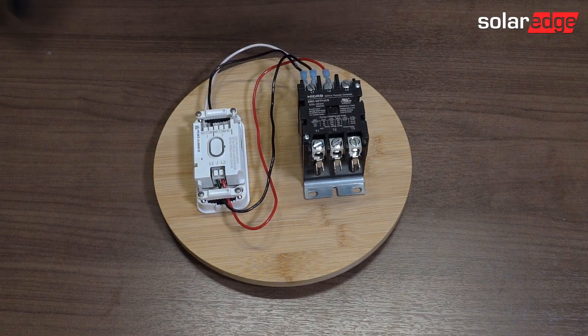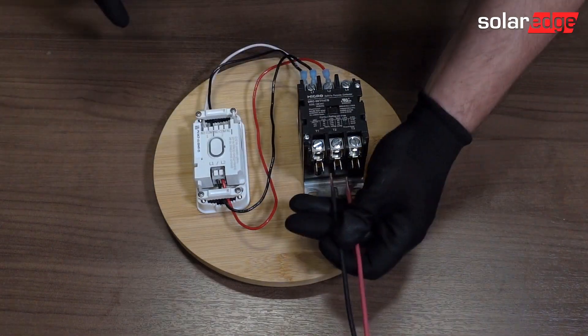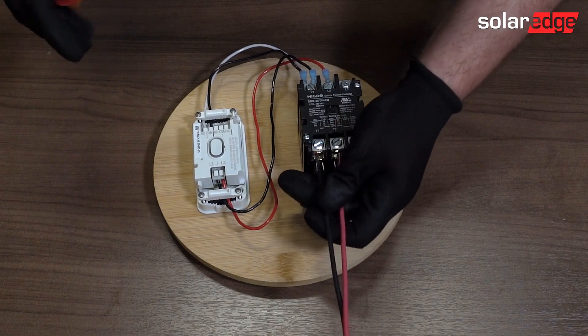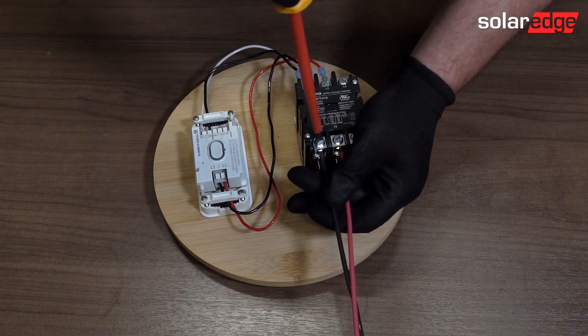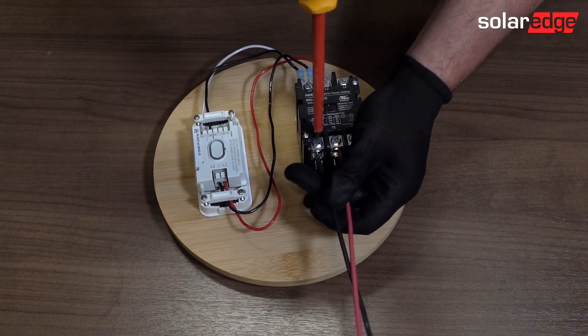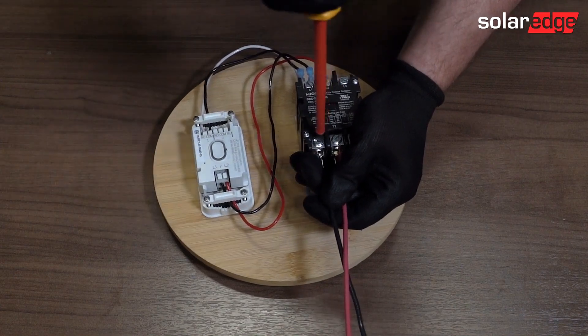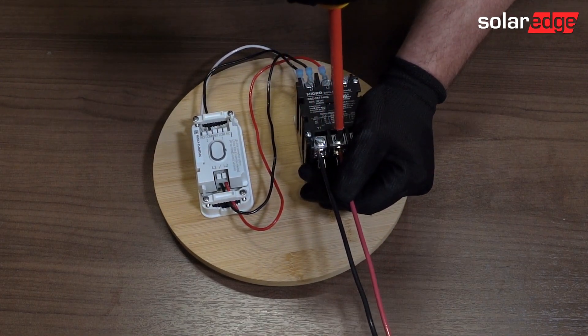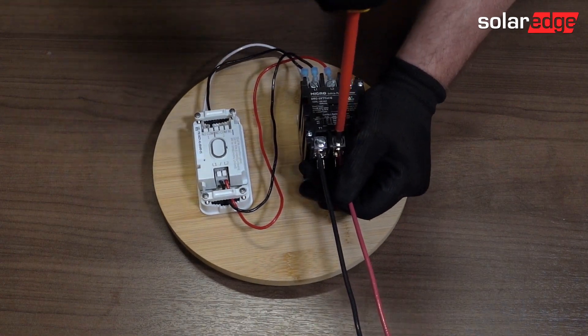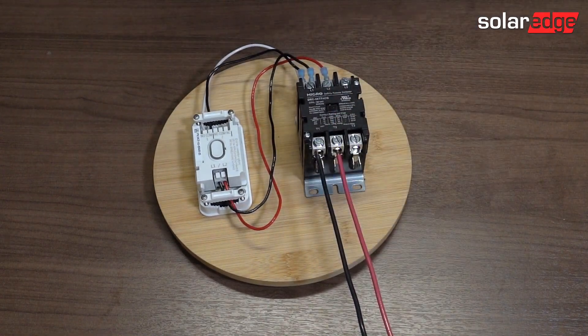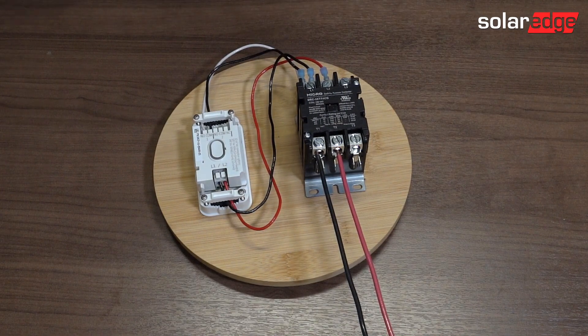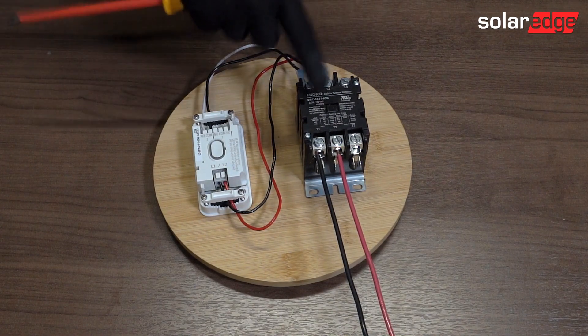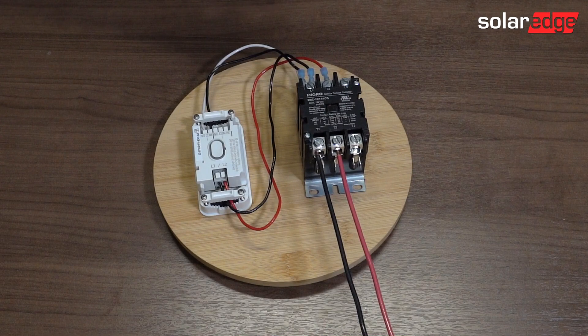Okay, so now we're going to wire from the load side to our load. And so I'm just going to do line one and line two. You know, you never switch the neutral, so that's why you don't see me adding a neutral here. Okay. And now we're going to go from the breaker to the supply side of the contactor.